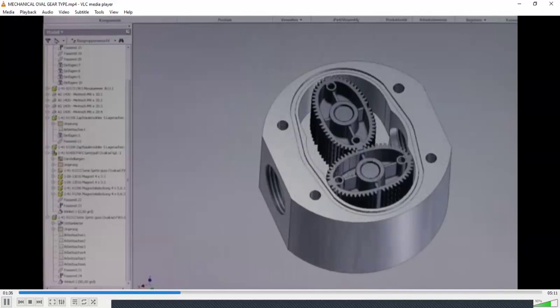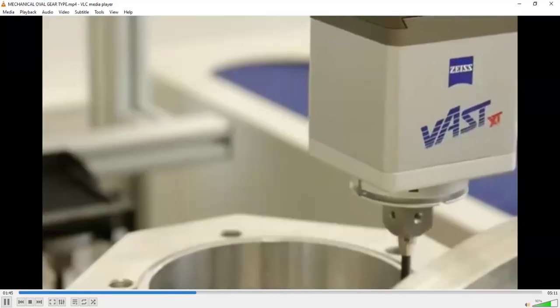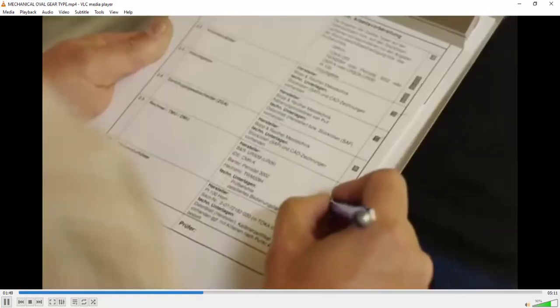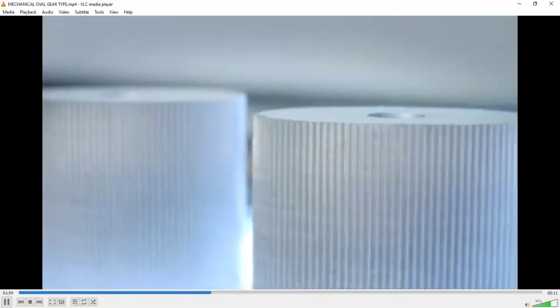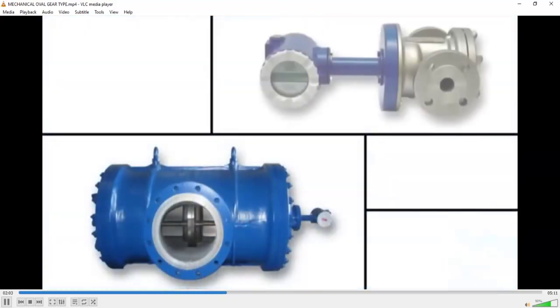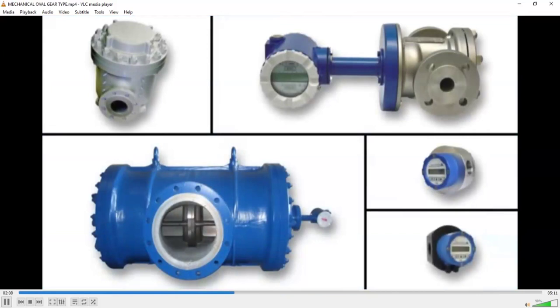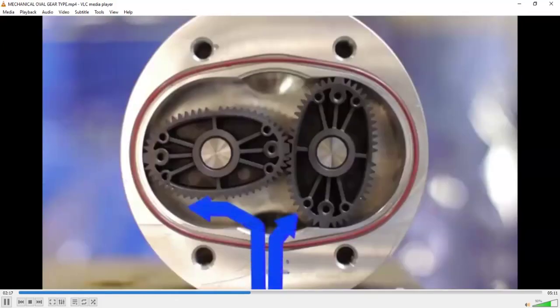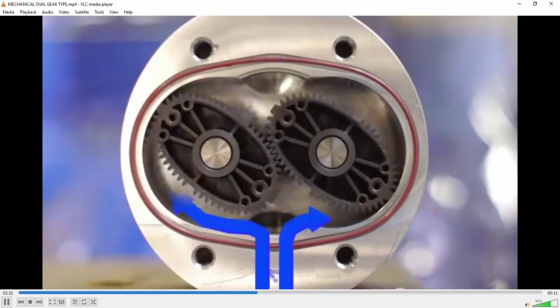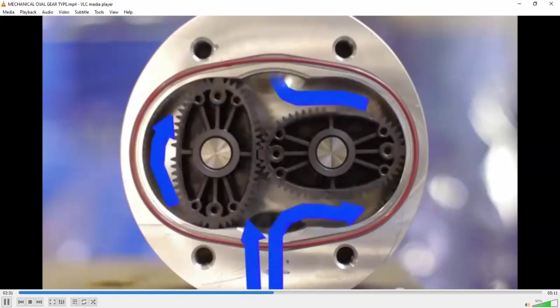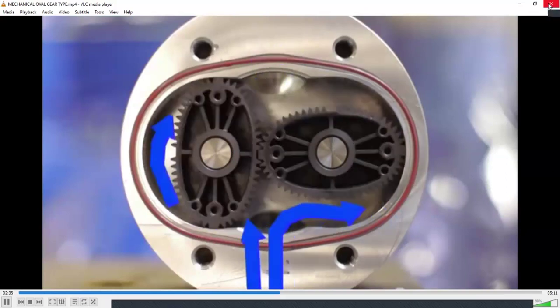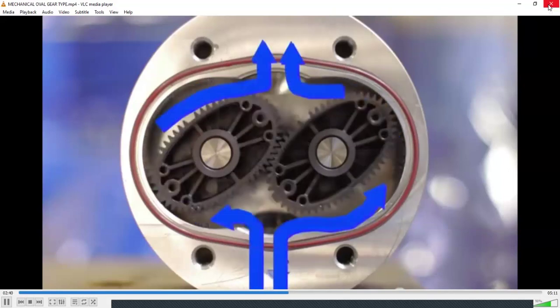Thanks to its simplicity and robustness, the oval gear meter is a measuring instrument for liquid flow measurement with convincing properties in terms of accuracy, repeatability, and durability. Measurement accuracies in the range of plus or minus 0.1% of measured value and a lifetime of 40 years are not uncommon. Depending on the version, the oval gear meter covers flow ranges from 0.01 liters per minute to 20,000 liters per minute in a broad viscosity range. The operation is always identical and based on the proven positive displacement principle. Only two toothed oval gears are moving in their housing. These are driven only by the liquid flow and roll on each other without any need for external energy. With each revolution of the oval wheel pair, a defined quantity of liquid is transported through the meter. The number of revolutions is an accurate measure of the flow quantity.